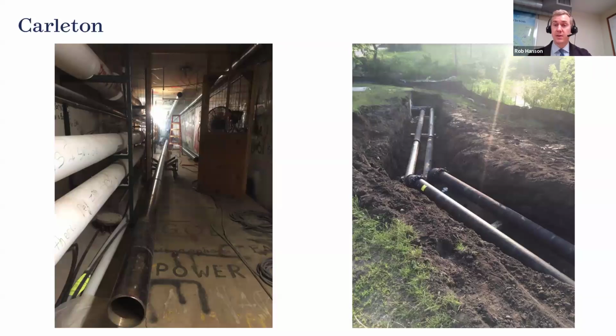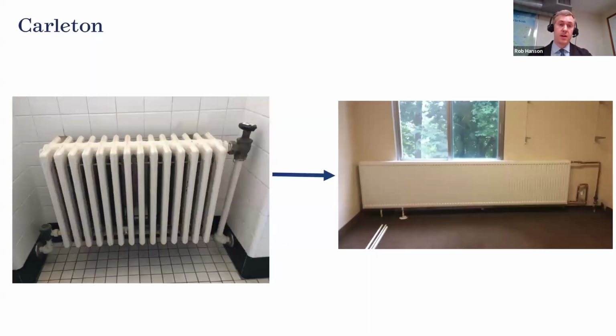We also had to update the buildings themselves. Older radiators need steam or very hot water to heat properly, but we were updating the system to hot water at about 120 degrees Fahrenheit. So we had to install a new style of radiator with more surface area to still heat rooms properly, and we also updated coils in air handlers — essentially small radiators within the ductwork.